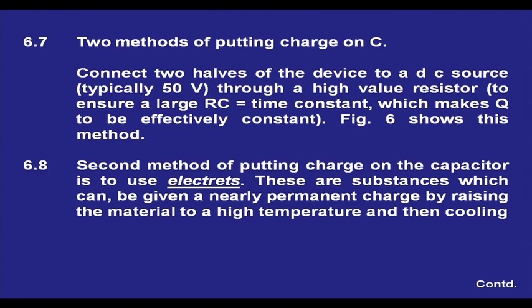And the second method is putting a charge on the capacitor using an electret. So, I can use an electret and charge it, and the microphone will hold the charge. But if there is humidity, then my electret may discharge. If it is discharged, then the sensitivity of the microphone will go down. So, by electret it is not that good, but putting a DC supply on the microphone is a very good arrangement. So, how do you do that?